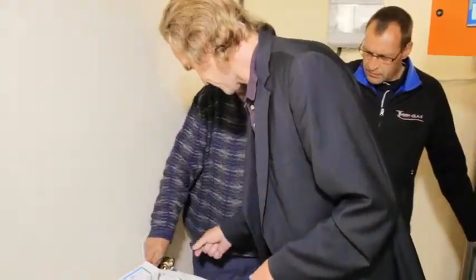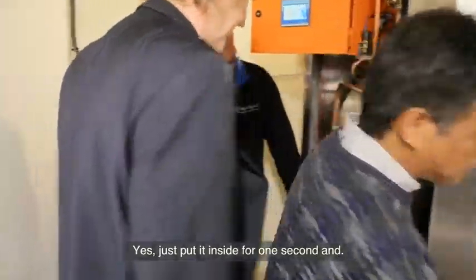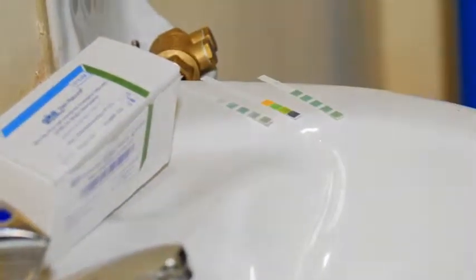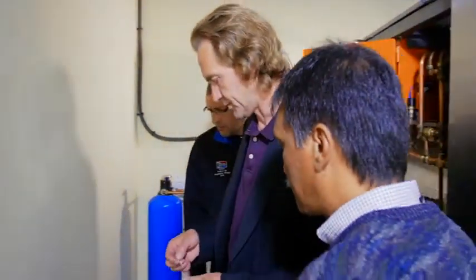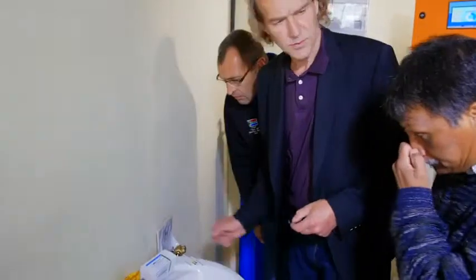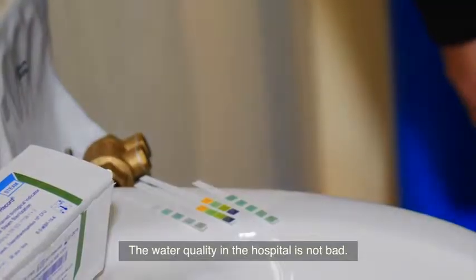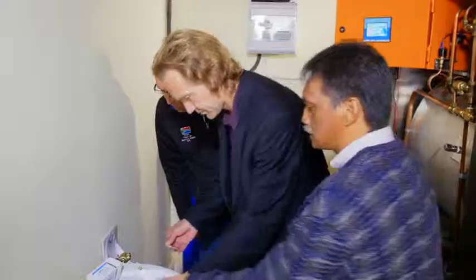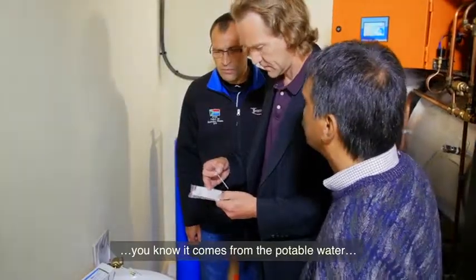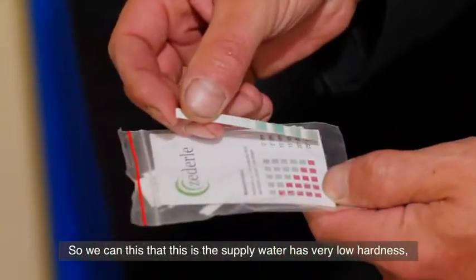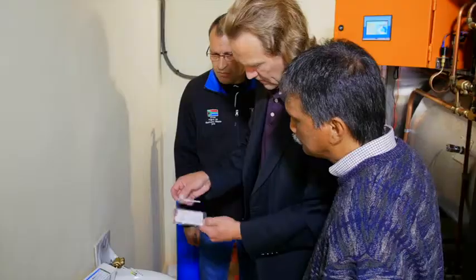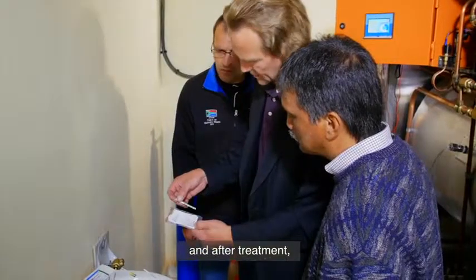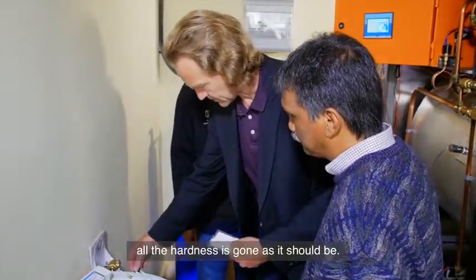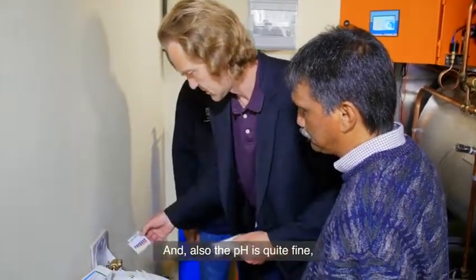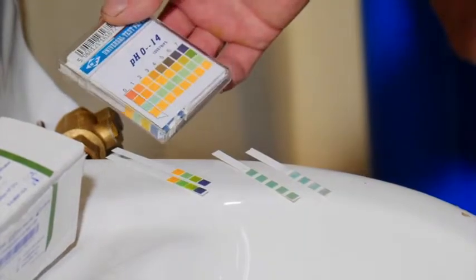Water's not hard. Yes, just put it inside for 1 second. The water quality in the hospital is not bad. But you know, it comes from the potable water normally. So we can see that already the supply water has a very low hardness. And after treatment, all the hardness is gone, as it should be. And also the pH is quite fine, in the range of 7.